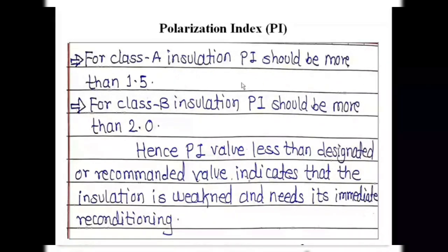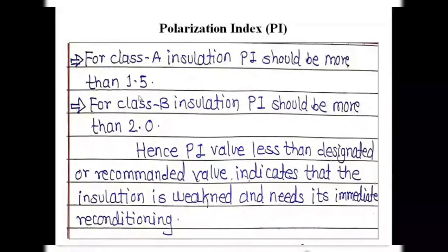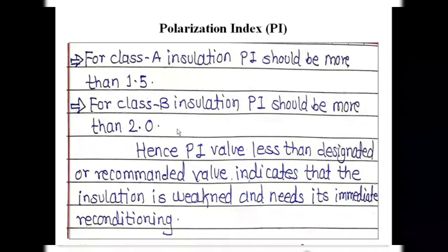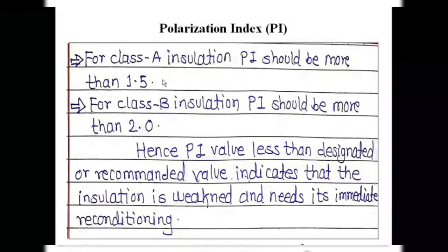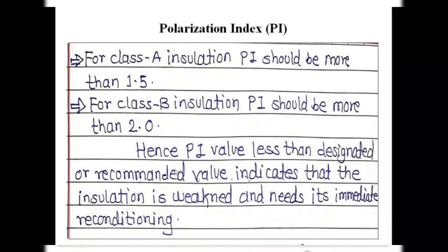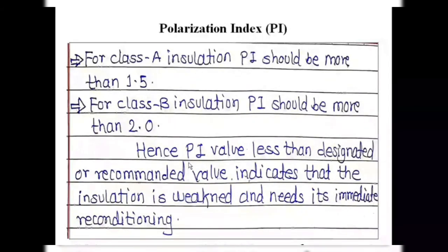For Class A insulation, the PI should be more than 1.5 for a healthy condition of the electrical equipment. The permissible PI value varies depending upon the class of insulation. If the value obtained is below the recommended limit for the given insulation class, immediate action must be taken. If the value is above the limit, the insulation is in good condition. The PI should be evaluated periodically as part of the maintenance schedule.